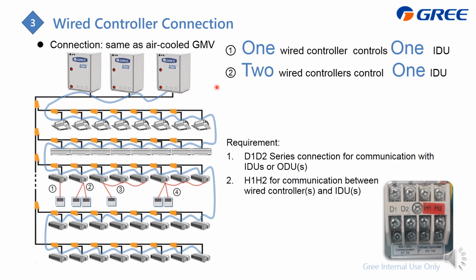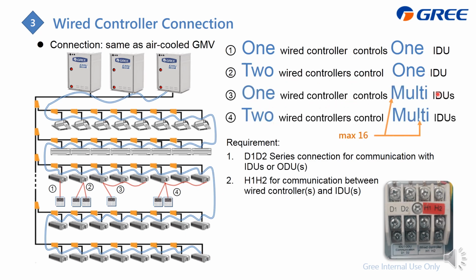And this is the wiring between the outdoor unit and the indoor units. The communication is the same as the air cool, from D1, D2 on the outdoor unit to all indoor units in series. For the wire controller, we support 1 wire controller controlling 1 indoor unit, 2 controlling 1, 1 controlling multi, and 2 controlling multi. The multi upper limit is 16. The wire controller connects to H1, H2, D1, D2 for the communication. And in this system, don't forget to wire the match resistor at the last D1, D2.